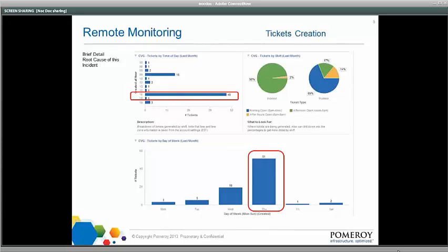And I think overall, in less than a 24-hour period of time, that secondary device was restored back to normal. Doug, do you have any commentary on that event? No, not really. It played out just like you said. We had a secondary power supply go bad. It was ordered, it was brought in within 4 hours, and Scott put it in and got it up and running. So yep, it wasn't a failure.